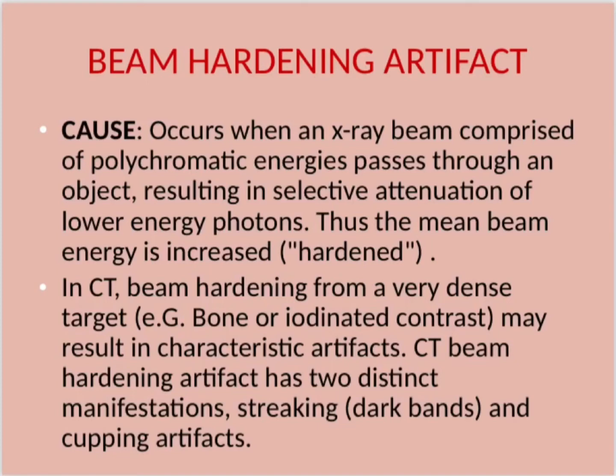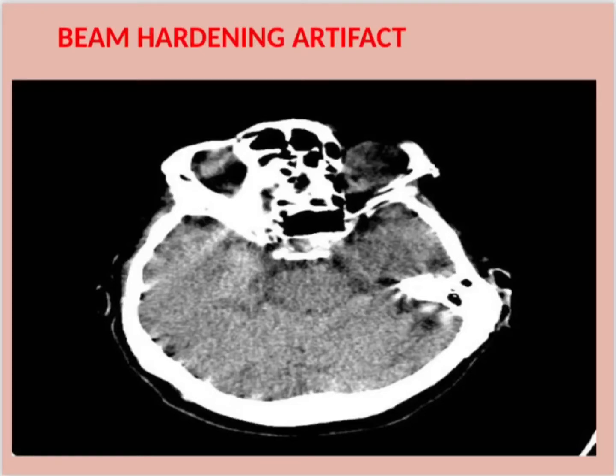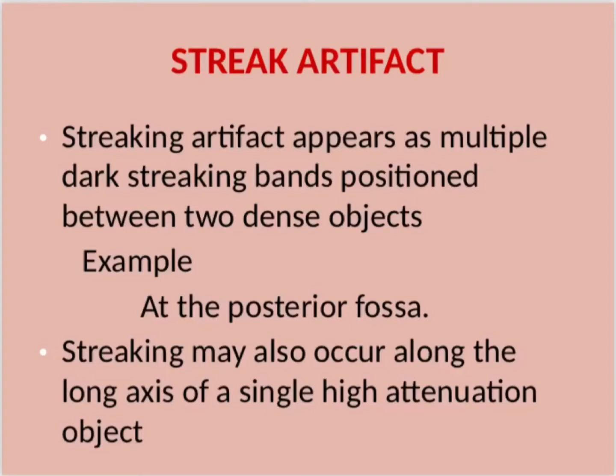CT beam hardening artifact has two distinct manifestations: streaking dark bands and cupping artifacts. Streak artifact appears as multiple dark streaking bands positioned between two dense objects — for example at the posterior fossa. Streaking may also occur along the long axis of a single high-attenuation object.